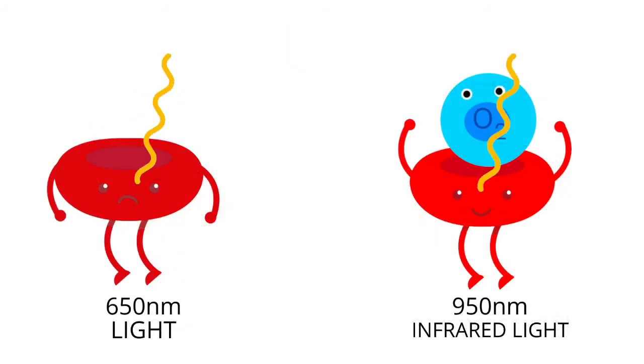You probably know that each color we see refers to a particular wavelength of light. For example, blue light has a wavelength of around 400 nanometers. The red color of deoxygenated blood absorbs 650 nanometer light. The oxygenated blood, which has a different shade of color, absorbs 950 nanometer light. This falls under the infrared light.